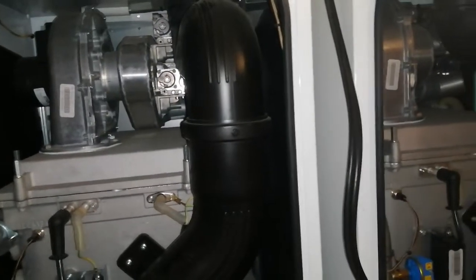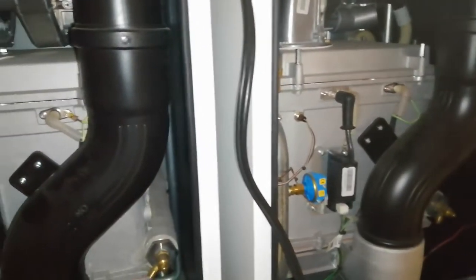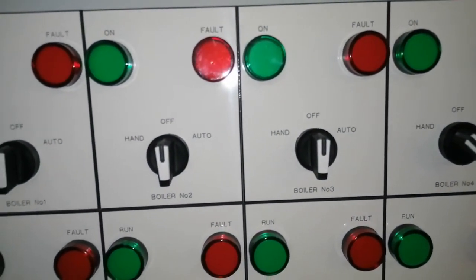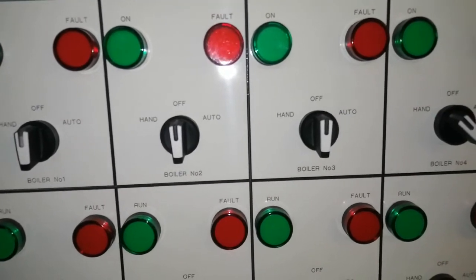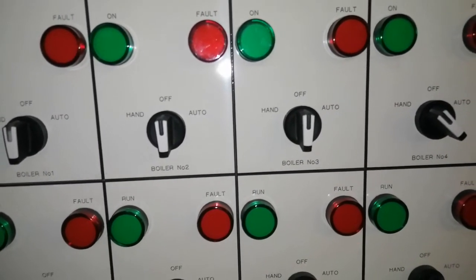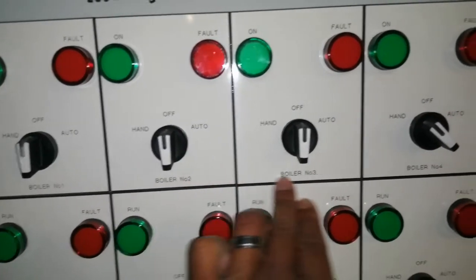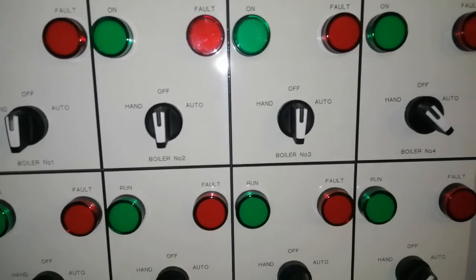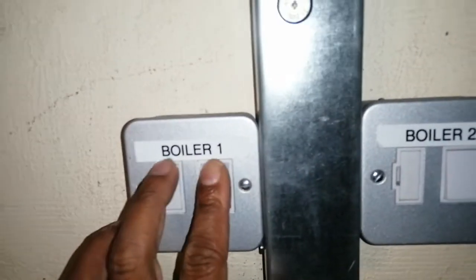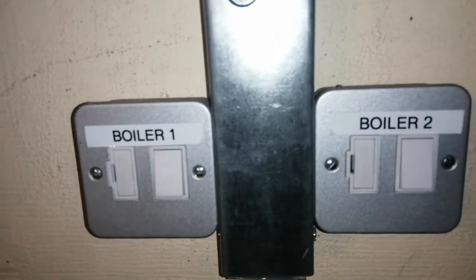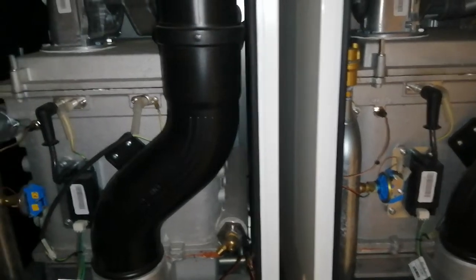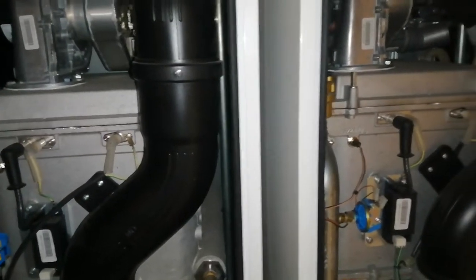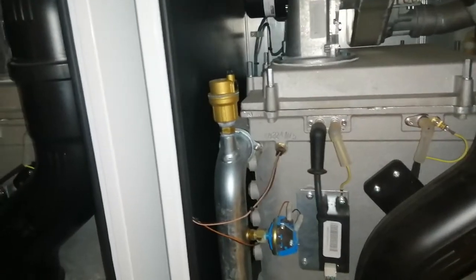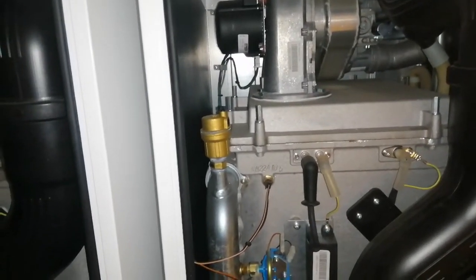That's another thing when you are carrying out servicing on these boilers. As you may already know, it's good to switch off a few of the boilers first once you arrive on site. So here on my BMS, I have shut them off, but despite shutting them off on the BMS, they're still running. So this is not controlling them, they're still operating. So I have 2 boilers here operating. I've shut the power off to these 2 boilers. I don't want my boilers overheating, otherwise when I'm analysing them I won't be able to get them up to temperature in order to check my high and low. So I've switched these 2 off. Ideally you want pump overrun on and so on with the boilers before switching them off.